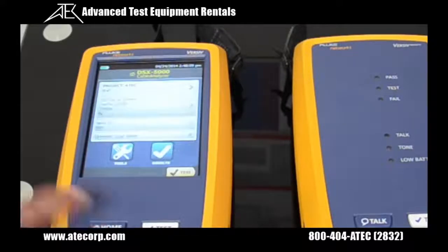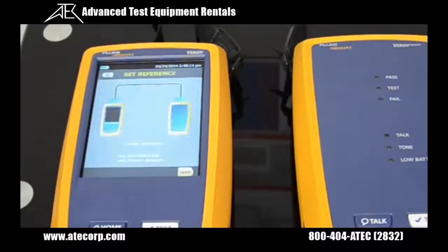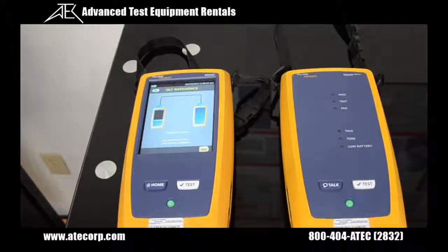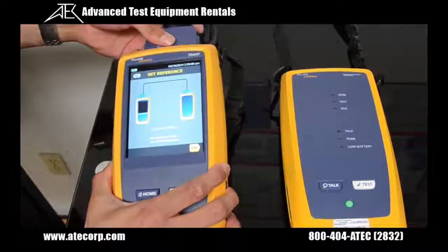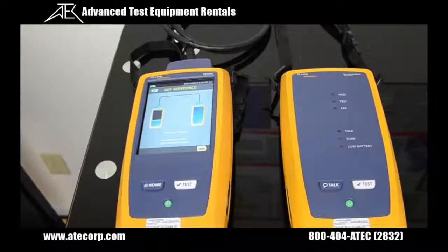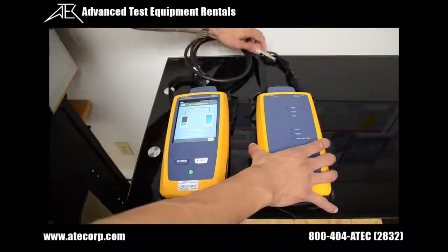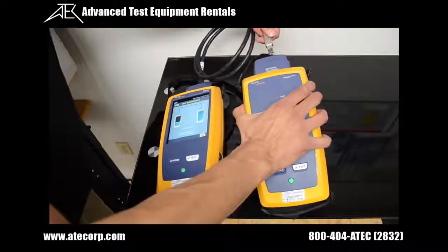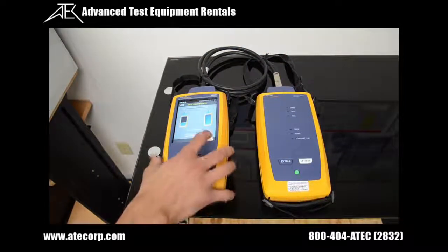Now I get to hit the home page, press tools, and set a reference. The reference is very important because you have to zero out your permanent link adapters and your channel adapters. The first thing I'm going to do is grab one of my permanent link adapters and connect it to my main unit. Next, I'm going to grab a channel adapter and connect that to my remote unit. Now install the permanent link adapter onto our channel adapter, and you should hear a beep after it's made connection. Now I'm going to press the test button.